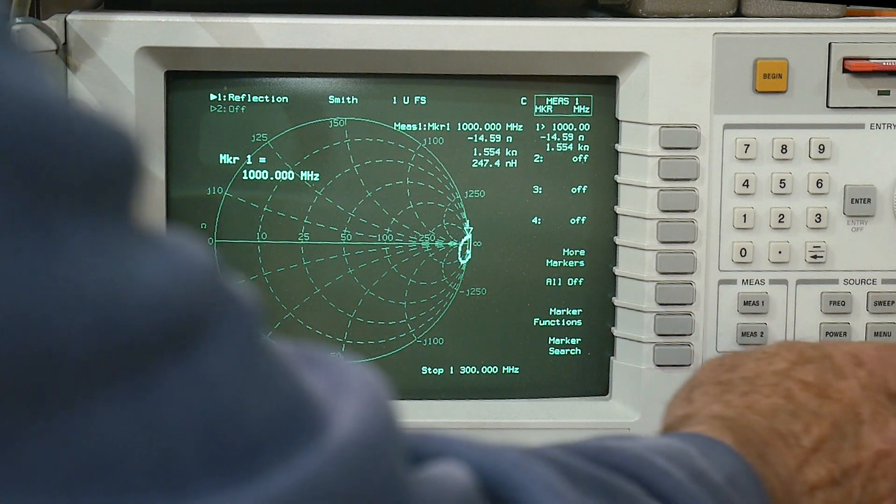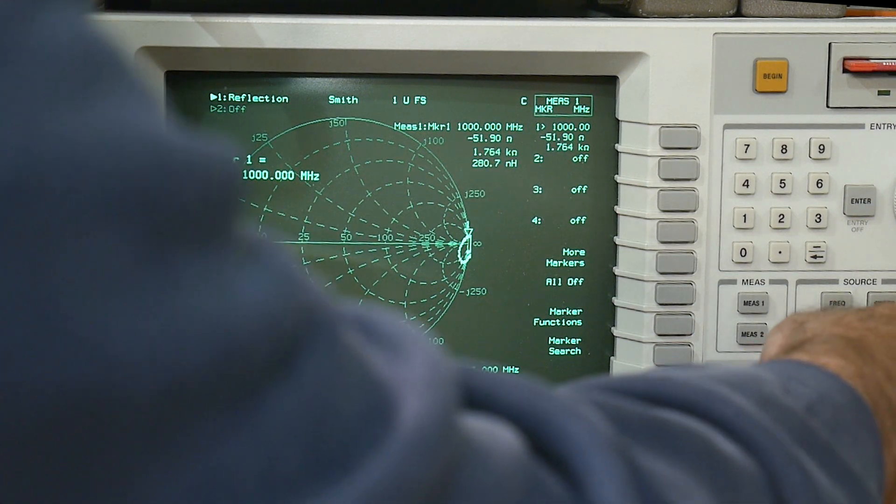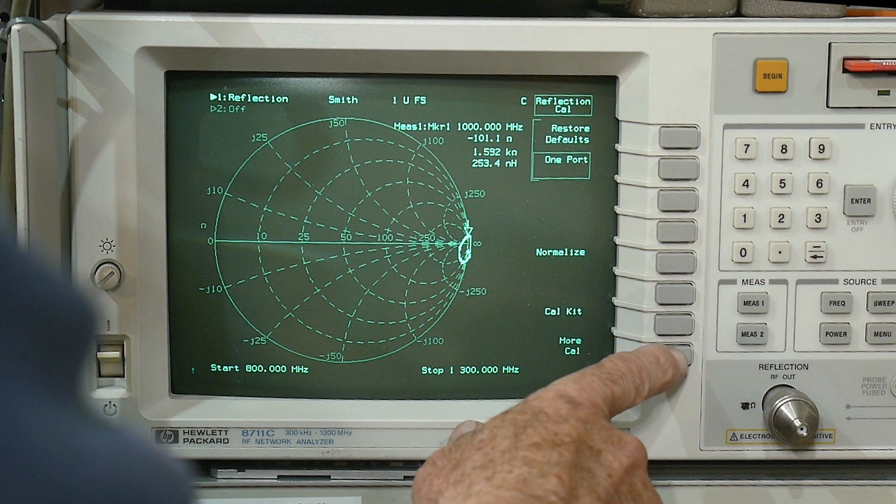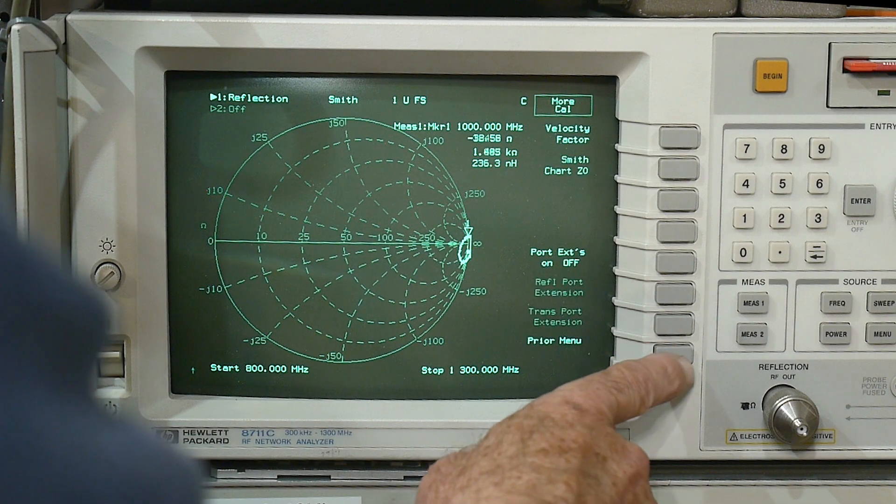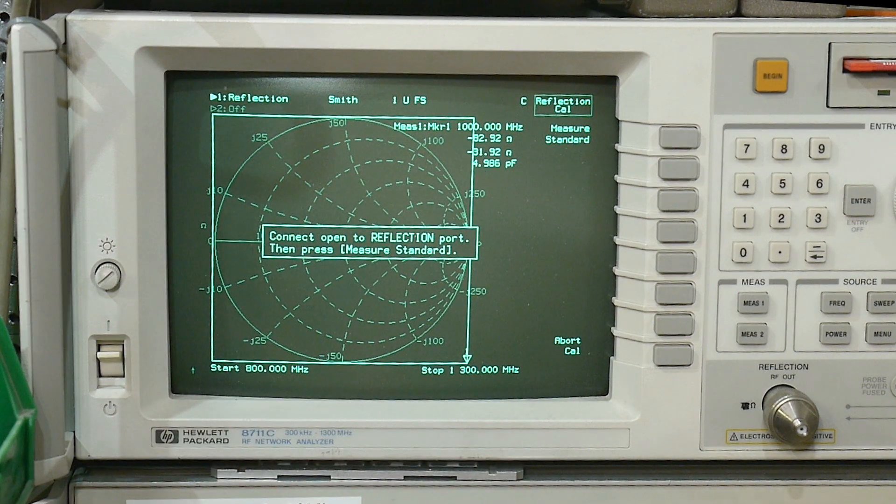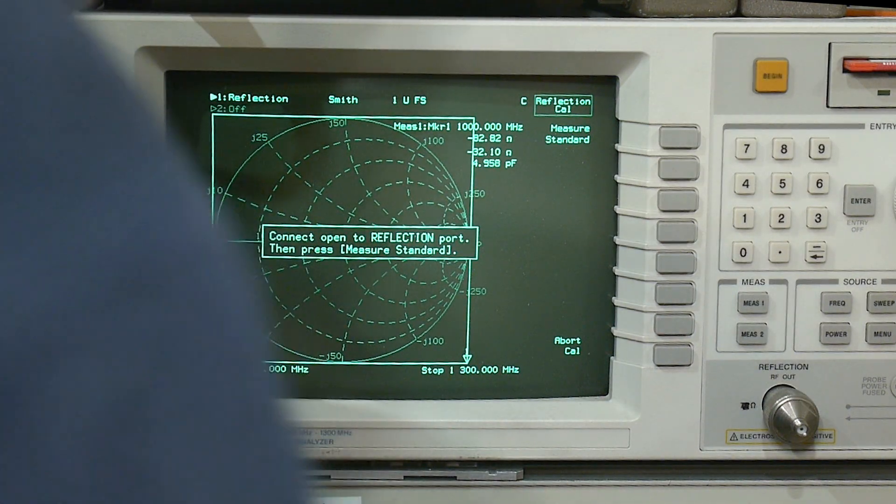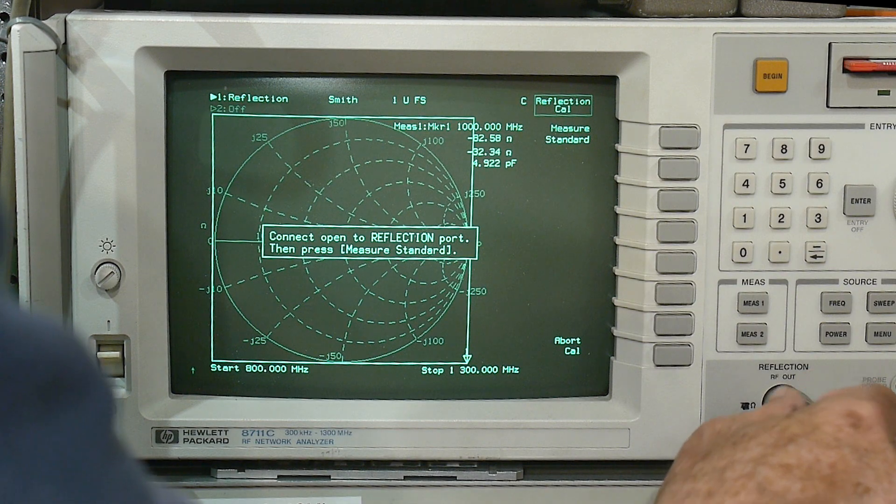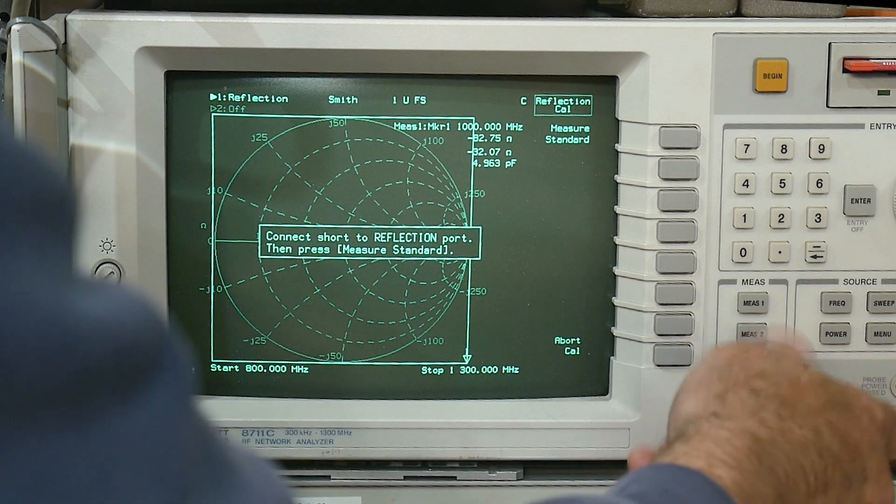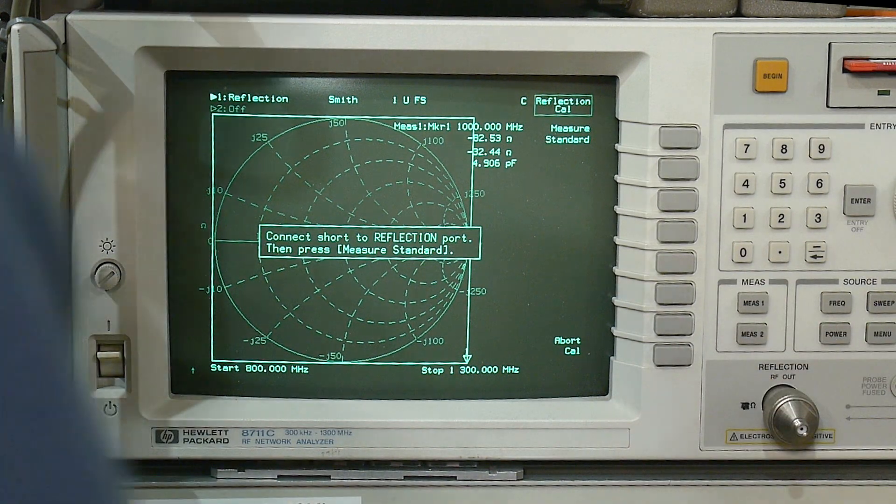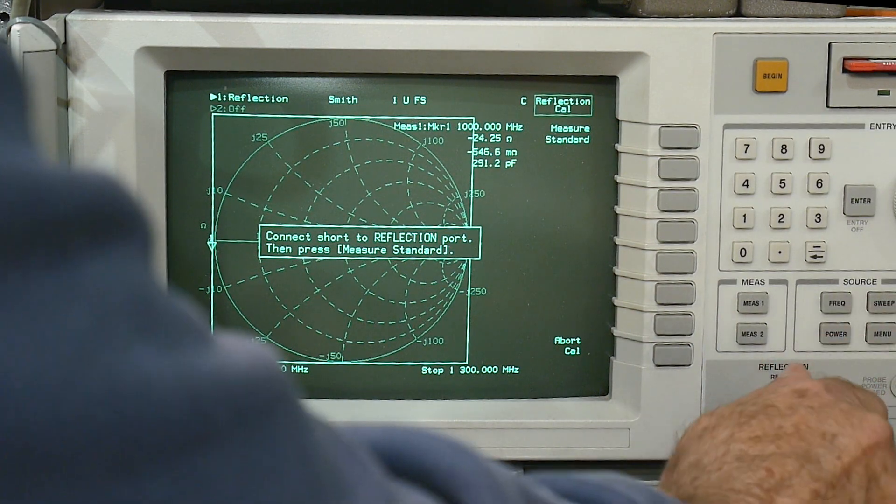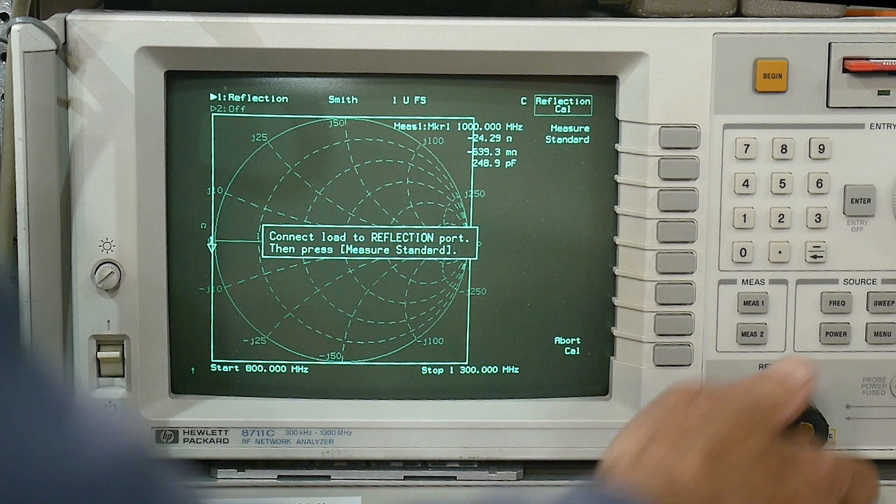And I think we should cal. So we will do, make sure I'm okay here. Yes, we will do a one port calibration. It says connect and open and open on short. And the load.